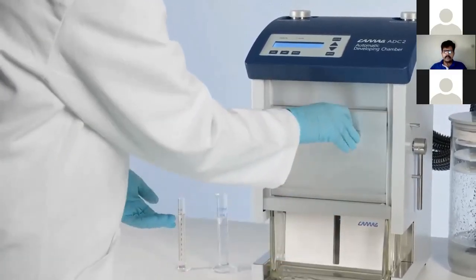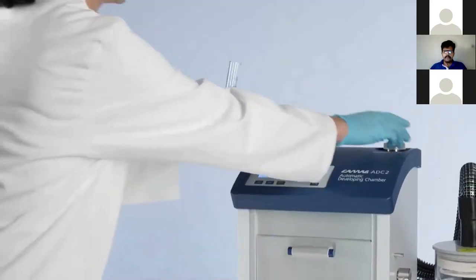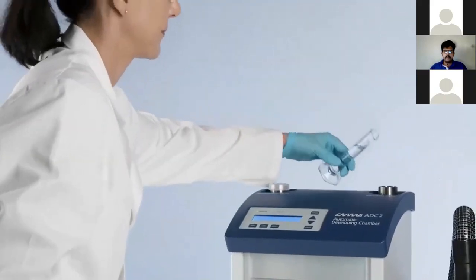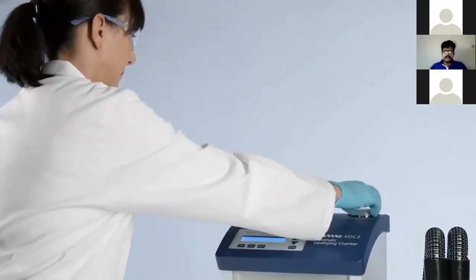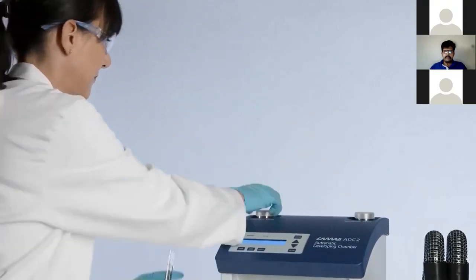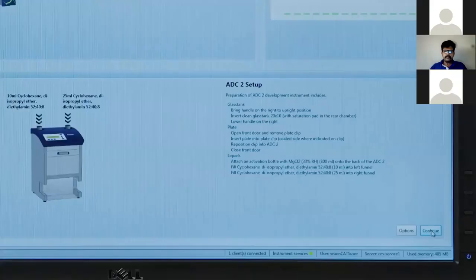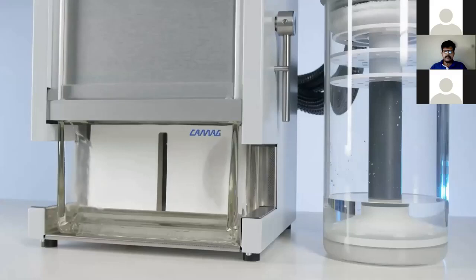After pouring, this entire process goes on for plate development. Pour in 10 milliliters of the mobile phase for the developing solvent, and 25 milliliters of the solvent for chamber saturation into the solvent ports, and execute the command. The entire process is monitored. The plate is developed in a saturated chamber if using the default settings.